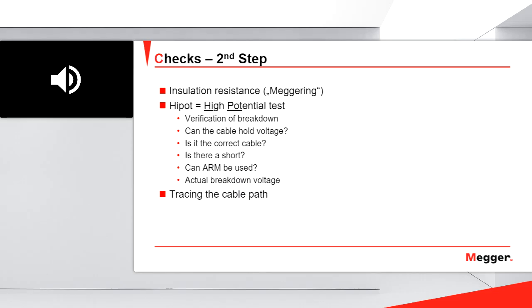The second step, as I said, is the checks or the verification. In this second step, I want to check which phase has a fault, the faulty cable. And the second piece of information I want to know is the breakdown voltage. What is the breakdown voltage of the fault?